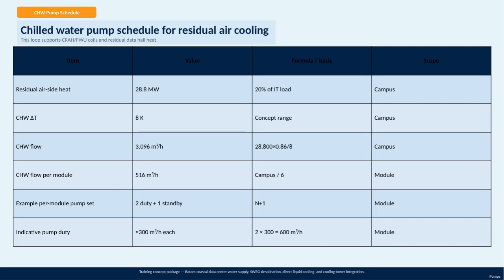Here we have the chilled water pump schedule specifically designed for residual air cooling. This loop plays a crucial role in supporting the CRAH/FWU coils, as well as managing the residual heat generated in the data hall. The training concept package focuses on the Batam Coastal Data Center, integrating water supply through SWRO desalination, direct liquid cooling, and cooling tower systems to optimize efficiency. Looking at the table, the residual airside heat is estimated at 28.8 megawatts, which accounts for about 20% of the total IT load across the campus.